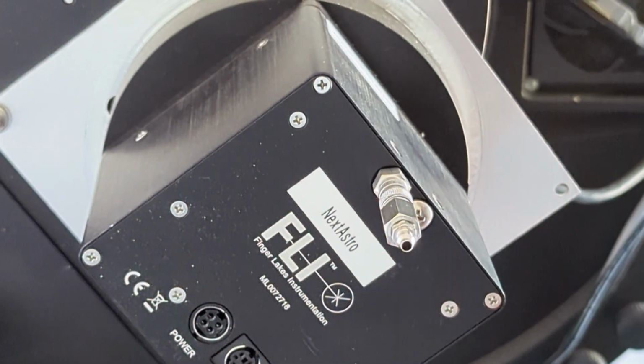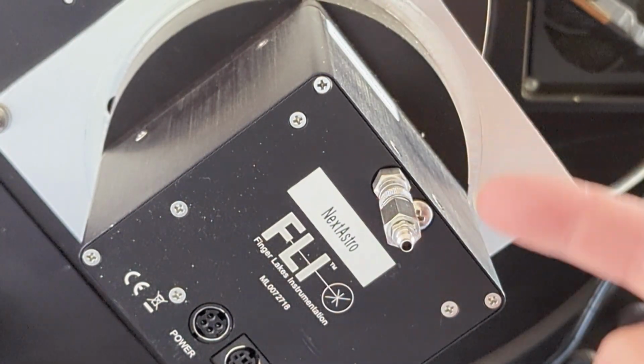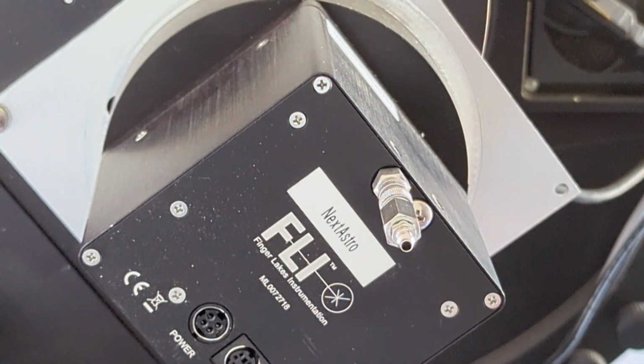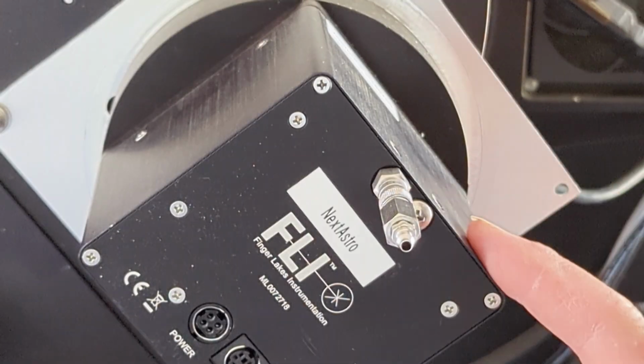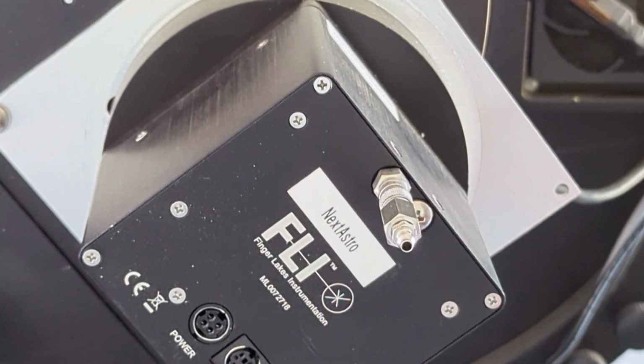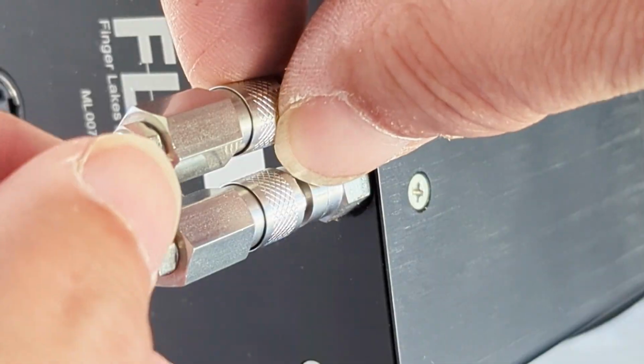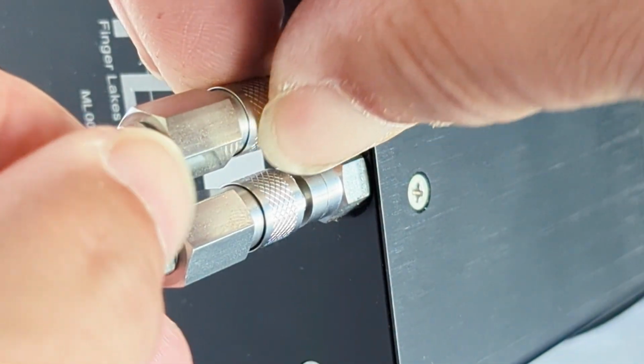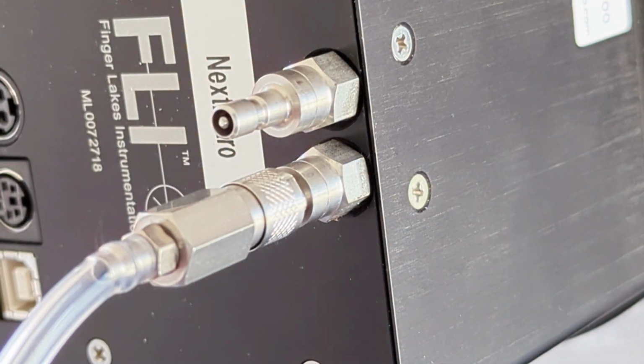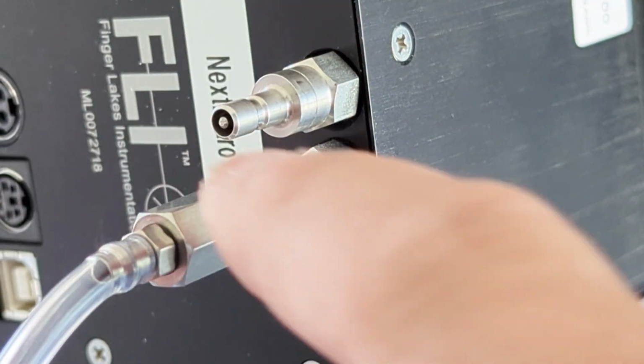You can see on the CCD there are no fans. It's only liquid cool, so we really didn't have a choice as to how we cooled this particular CCD. It disconnects, and there's a little valve in there to stop any leaks.